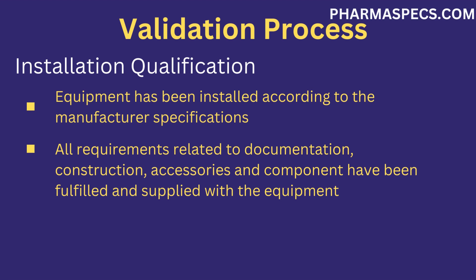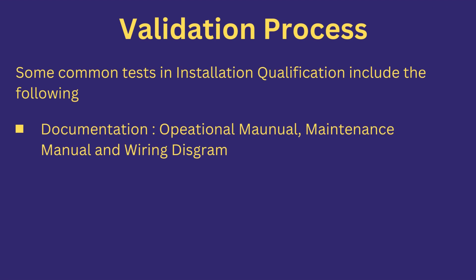The next stage after design qualification is installation qualification. In this stage, equipment installation is verified and checked to see whether the installation is carried out according to the equipment and manufacturer requirements. It is also checked that the supplied equipment contains all the required elements such as documentation, material of construction, accessories, and components. Some common tests in installation qualification include documentation — it is checked and verified that the manufacturer has supplied all documentation agreed upon during the design qualification stage, such as operational manual, maintenance manual, wiring diagram, and preventive maintenance schedule.